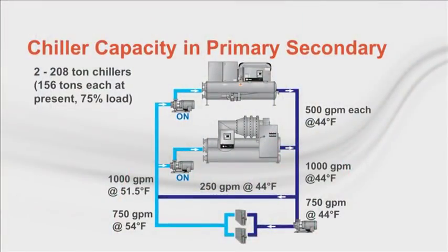Now let's move on to another common hiccup. The chillers waste capacity, and in most systems are incapable of being fully loaded due to system effects. So let's explore the effect that the primary-secondary system has on chiller capacity. To illustrate, we need to put flows and temperatures on our system drawing. In this case, we have the secondary side calling for 750 GPM of 44-degree water. Since our chiller pumps are sized for 500 GPM per chiller, we have both chillers on for a combined total of 1,000 GPM. A quarter of that, 250 GPM, is not needed by our two-way valves in the system and returns directly to the chillers through the decoupler pipe.